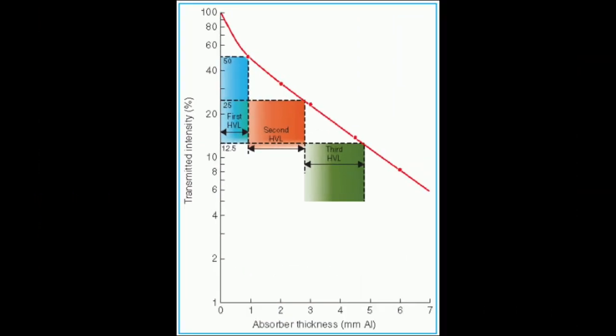Half-value layer is defined as the thickness of an attenuating material at which the intensity of radiation will be decreased by 1/2. Half-value layer, or HVL testing, provides important adjunct information to kVp testing about beam penetrability and with respect to type of rectification, applied kV, and total filtration of the primary beam. Recall that total filtration is important for radiation protection as well as image quality by absorbing and thereby eliminating photons that are too low energy and will therefore not contribute to useful information hitting the receptor and only contribute to patient dose. When testing HVL, it's important to be able to evaluate for discrepancies.